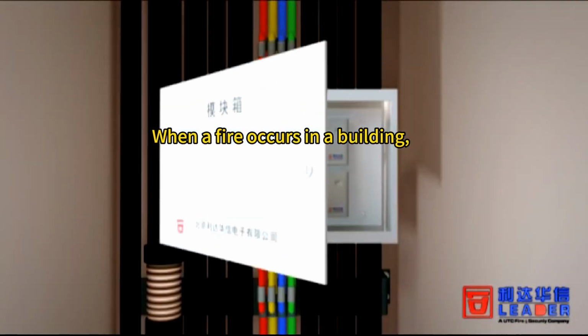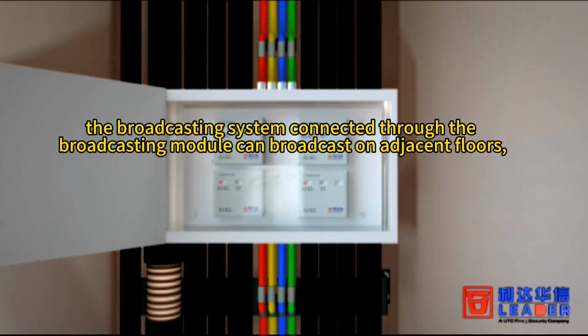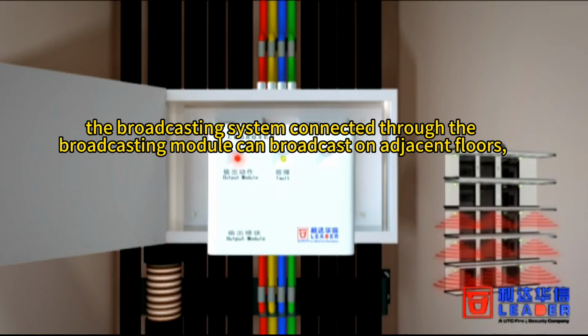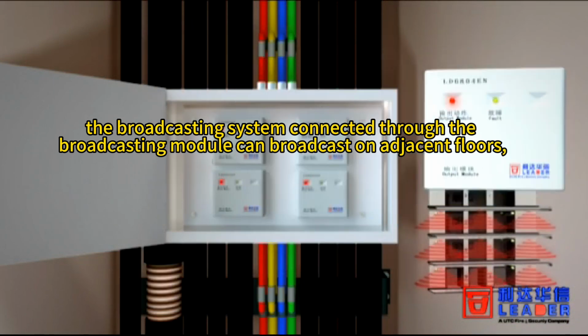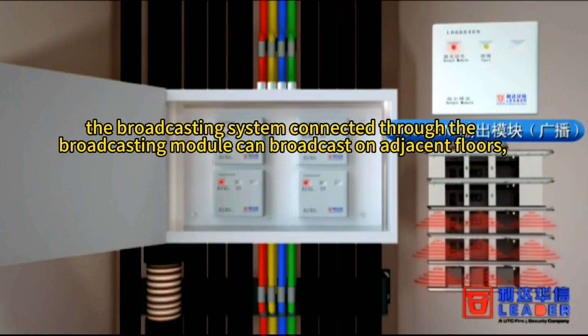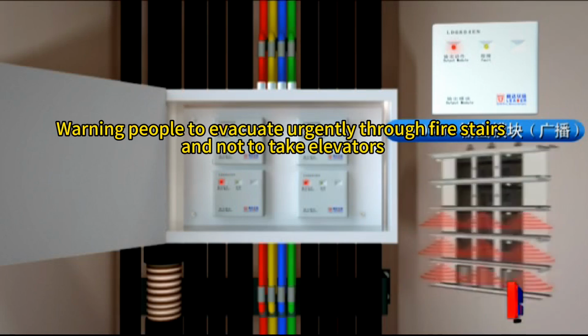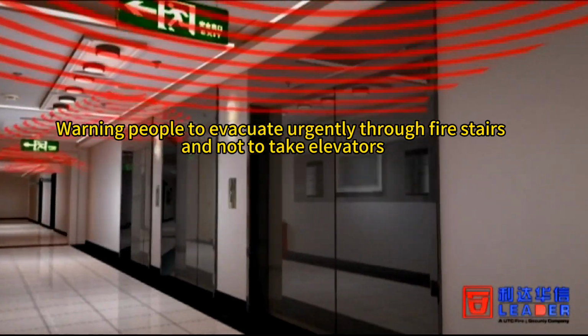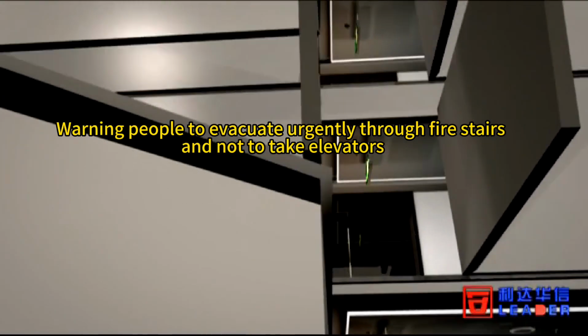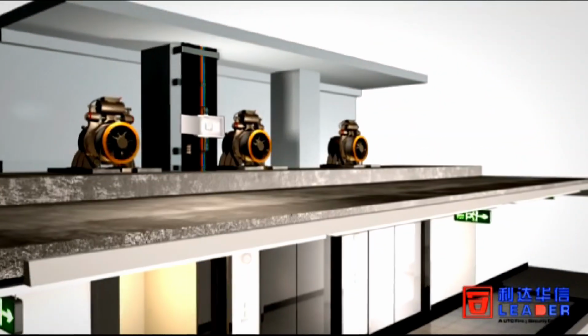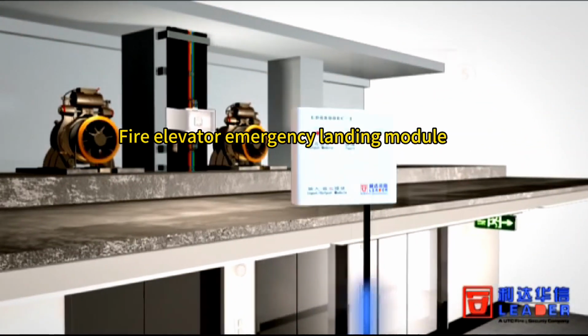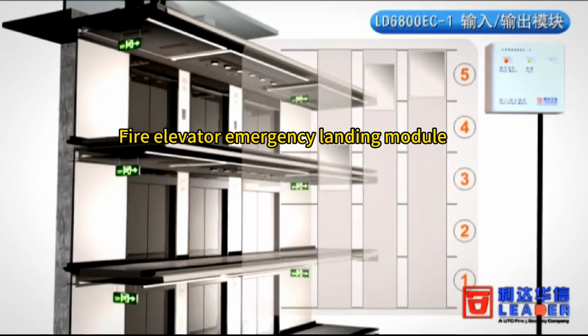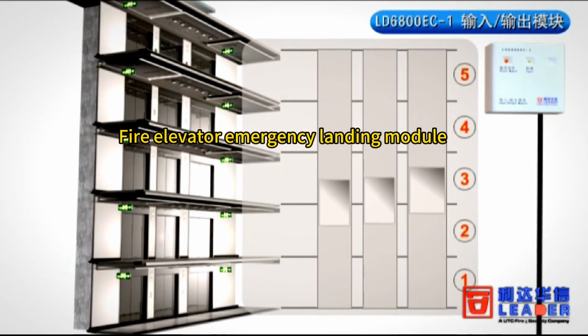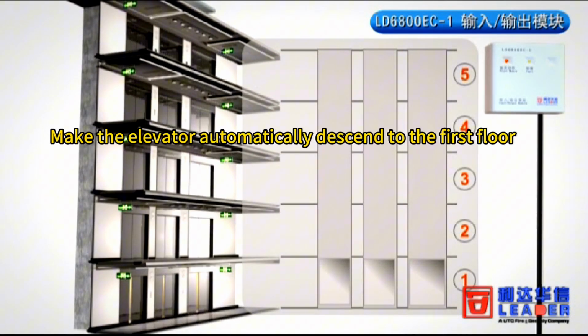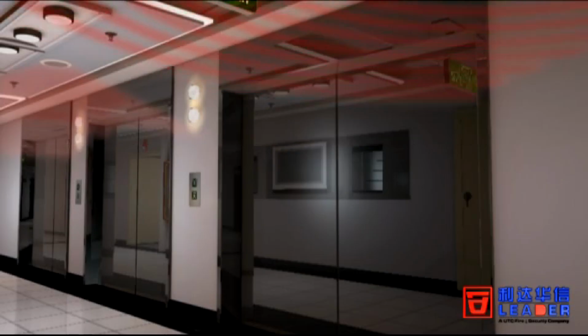When a fire occurs in a building, the broadcasting system connected through the broadcasting module can broadcast on adjacent floors, warning people to evacuate urgently through fire stairs and not to take elevators. Fire elevator emergency landing module. Make the elevator automatically descend to the first floor.